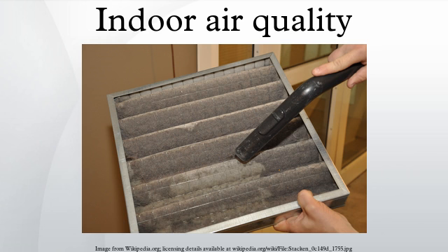Indoor CO2 levels are an indicator of the adequacy of outdoor air ventilation relative to indoor occupant density and metabolic activity. To eliminate most complaints, the total indoor CO2 level should be reduced to a difference of less than 600 ppm above outdoor levels. The National Institute for Occupational Safety and Health considers that indoor air concentrations of carbon dioxide that exceed 1000 ppm are a marker suggesting inadequate ventilation.